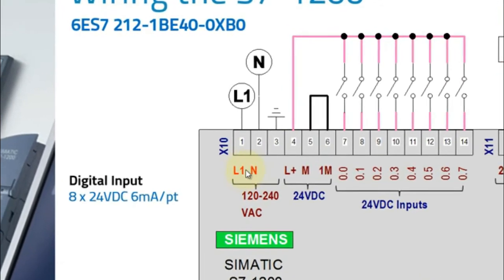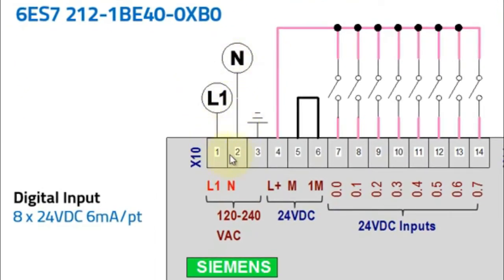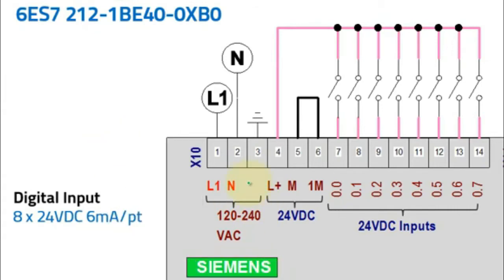Starting with wiring the S7-1200: line one and neutral are given from the power source to energize the PLC, providing power to all the inputs and the processor. Then you have a 24 VDC output — L+ and M. This 24 VDC is converted from AC; the AC is converted to DC by the power supply already inside this PLC. This DC can be used for various purposes.